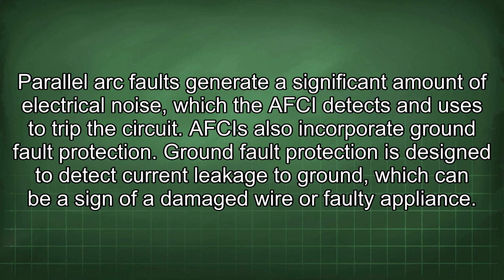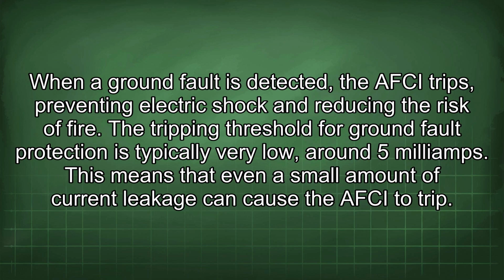AFCIs also incorporate ground fault protection. Ground fault protection is designed to detect current leakage to ground, which can be a sign of a damaged wire or faulty appliance. When a ground fault is detected, the AFCI trips, preventing electric shock and reducing the risk of fire. The tripping threshold for ground fault protection is typically very low, around 5 mA. This means that even a small amount of current leakage can cause the AFCI to trip.